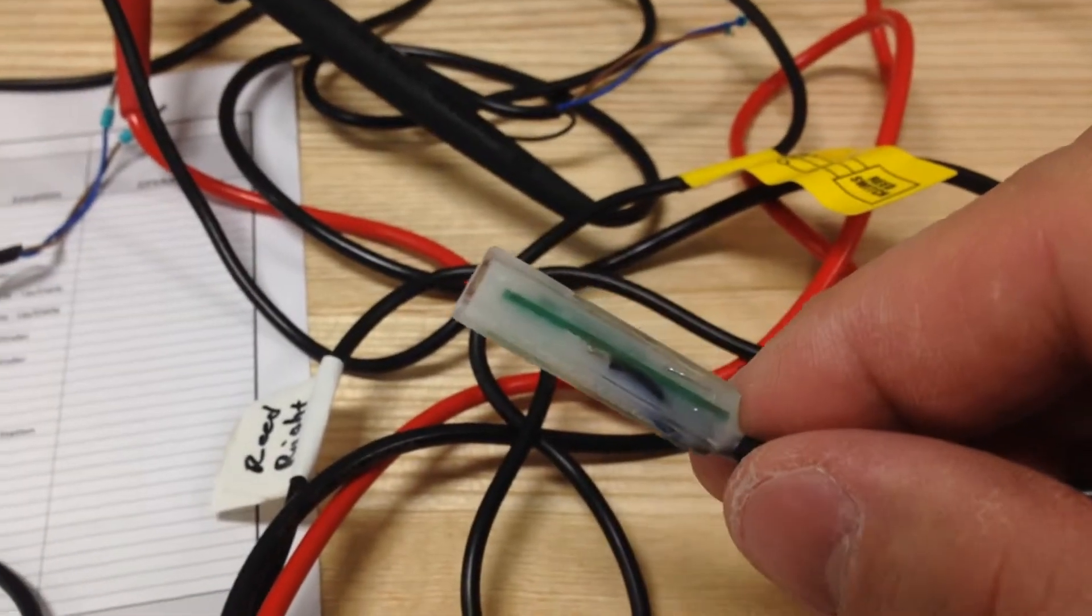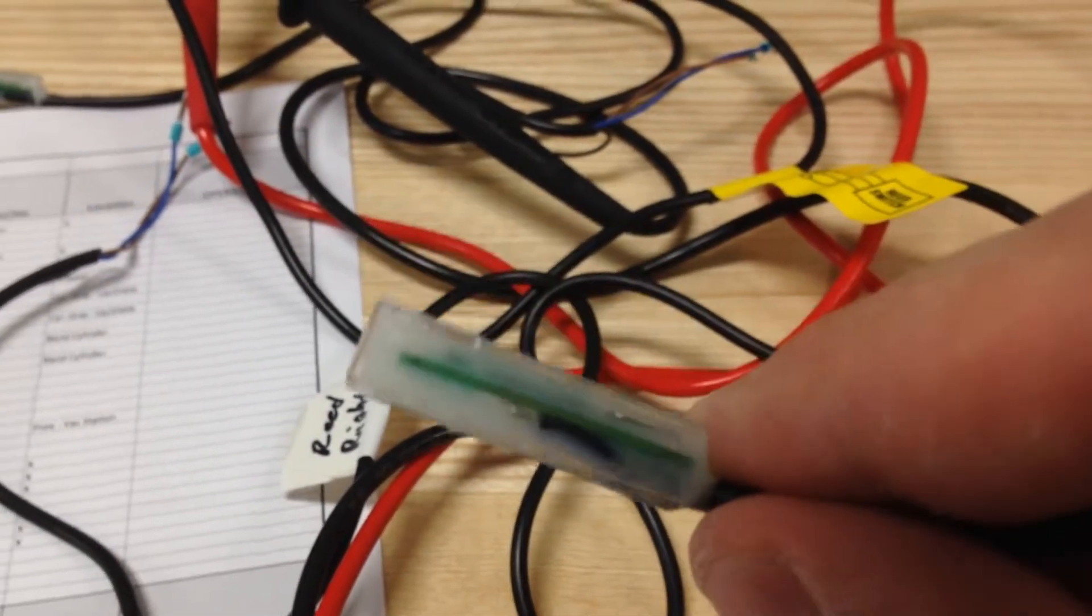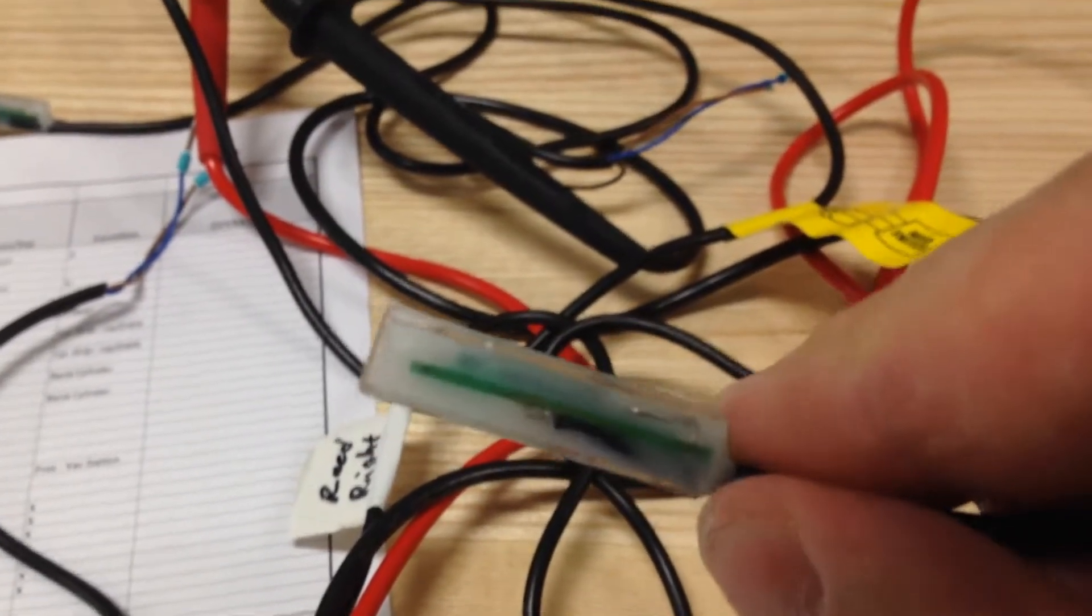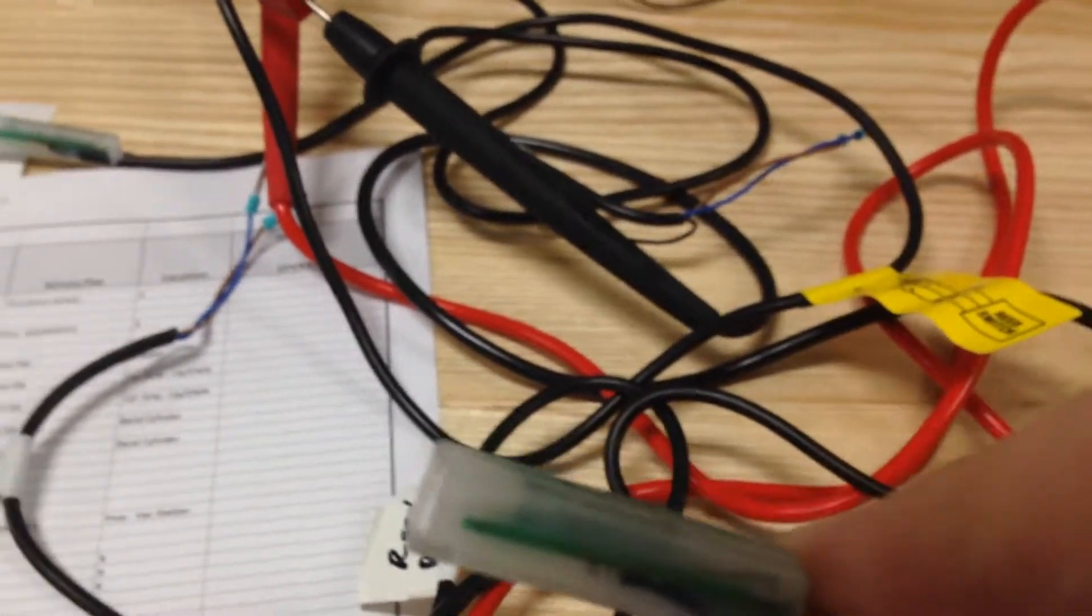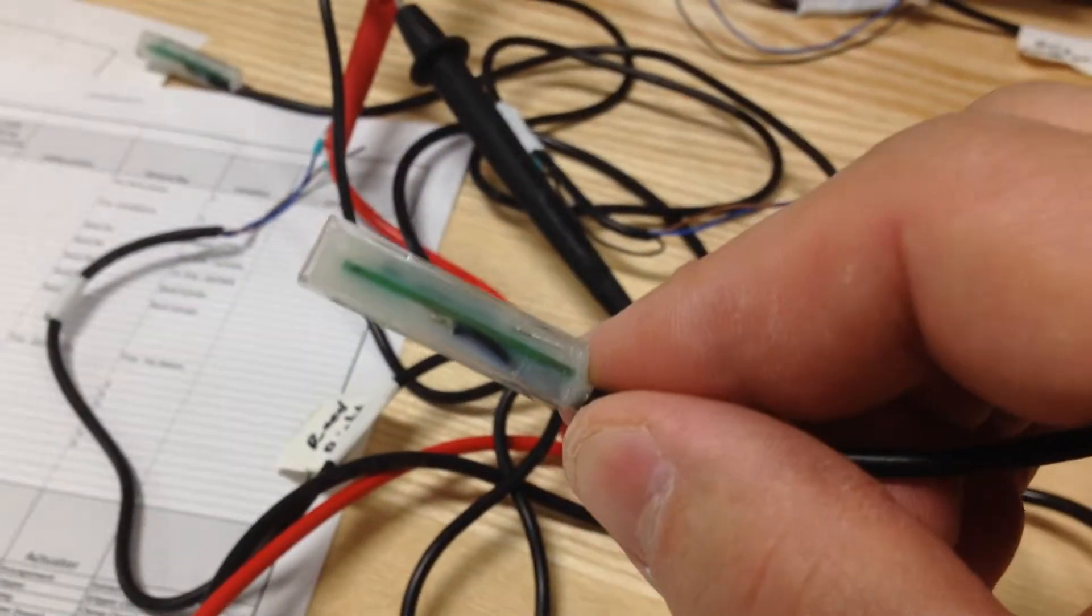But luckily, they kind of got fused or welded. The reed switch that acts with a magnet got welded inside this and we just tapped them a couple of times and broke them free.